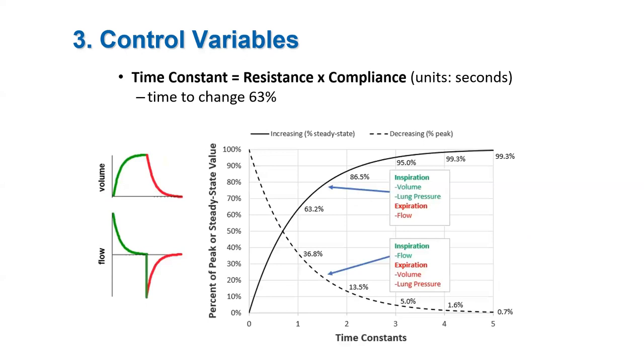A key concept in the understanding of ventilator waveforms is the idea of a time constant. The time constant is a characteristic of exponential curves as seen in the inspiratory volume and flow waveforms during pressure control. The time constant is calculated by multiplying resistance by compliance with the resulting units of time, usually seconds. In a unit of time equal to one time constant, an exponential curve will change by 63%. This is important for determining whether volume and flow curves represent normal or abnormal respiratory system mechanics. A rule of thumb is that a long time constant generally means an increased resistance, whereas a short time constant usually means a decreased compliance.